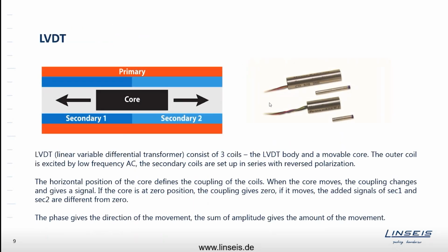Regarding the detectors, speaking about basic instruments, regarding the detectors of all our dilatometers, we have two different approaches to get a sample reading. First of all, most of our instruments work with a classical so-called LVDT, a linear variable differential transformer, or basically an electric magnet. On the right side, you see a picture. On the left side, you see a schematic drawing.